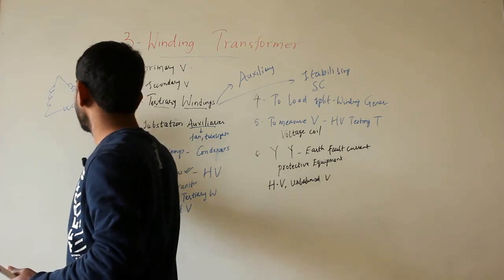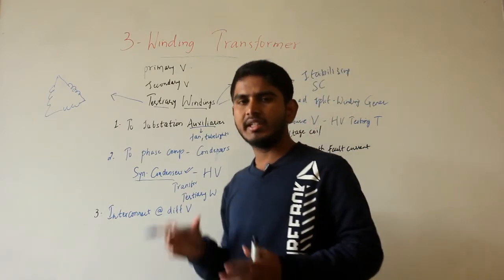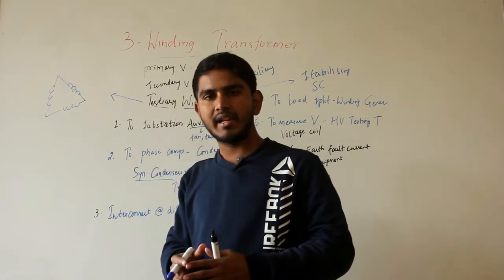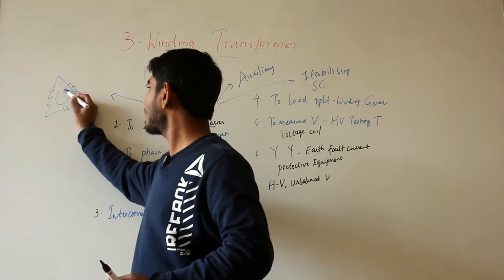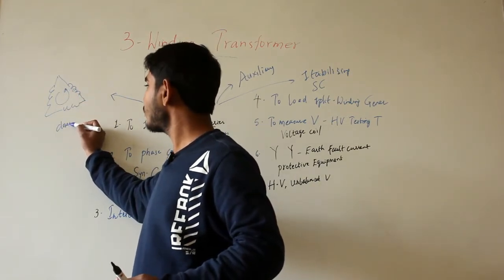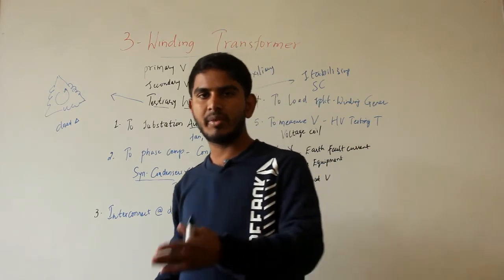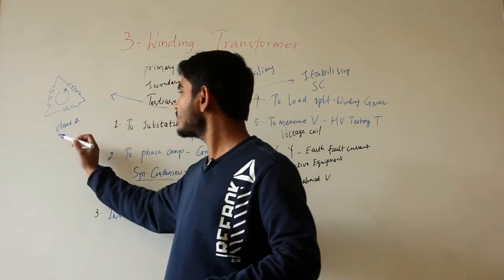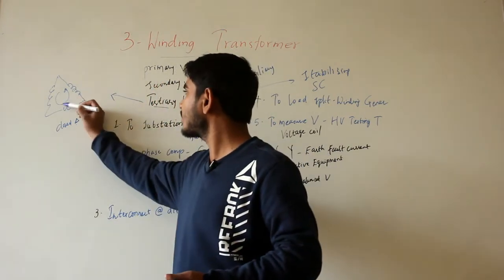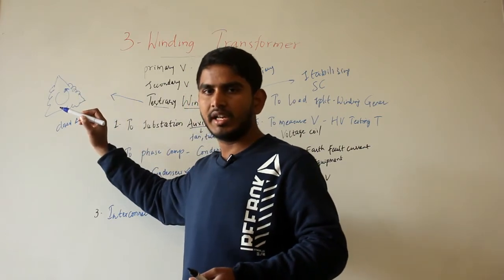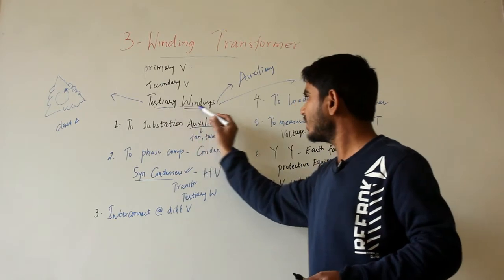The tertiary winding can also be called a stabilizing winding when it is employed to limit the short-circuit current in the star-star connected transformer. Normally, tertiary windings are delta-connected windings. Whenever a short circuit or fault occurs on the primary and secondary sides, any considerable unbalance in phase voltages can be compensated by the circulating currents flowing in the closed delta. The reactance of these windings must be large enough to limit the circulating currents and ensure the heating capacity of these windings.